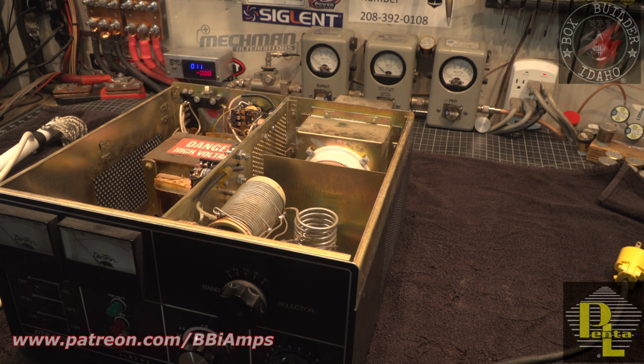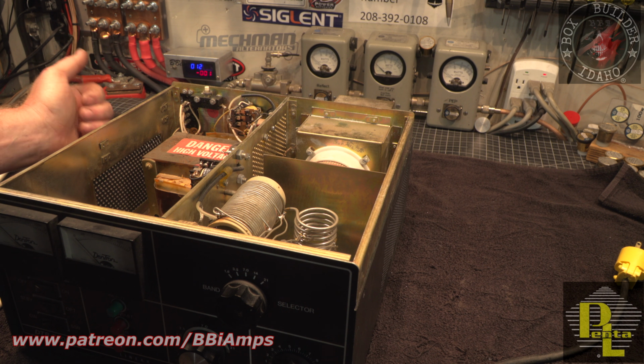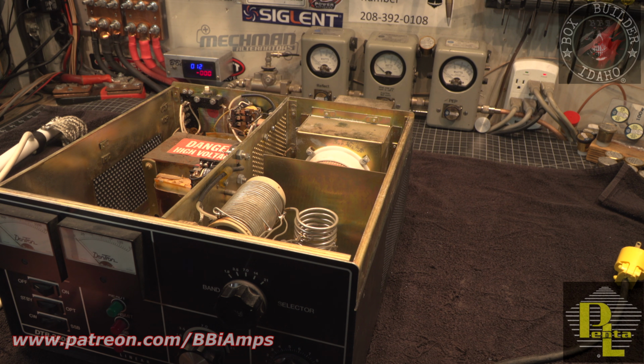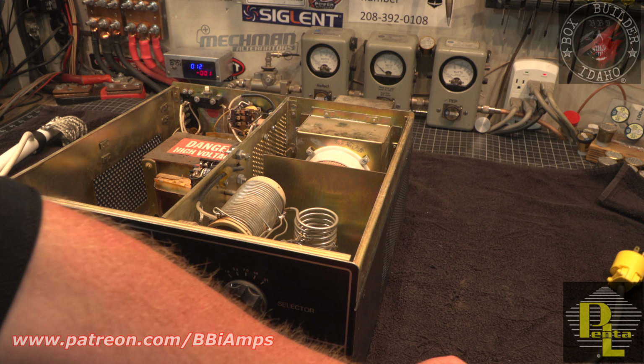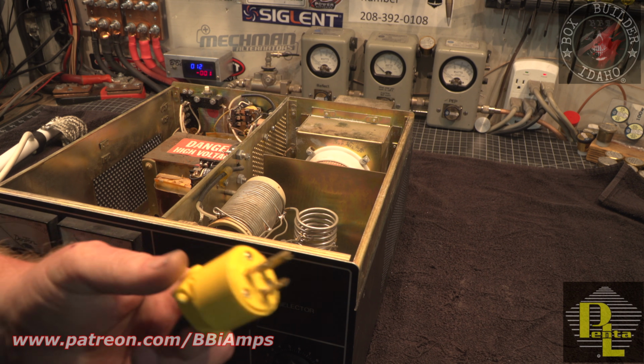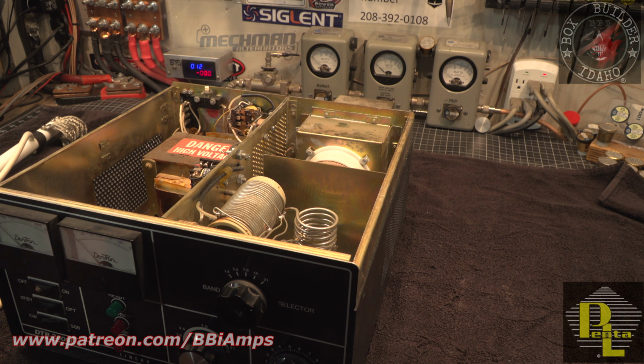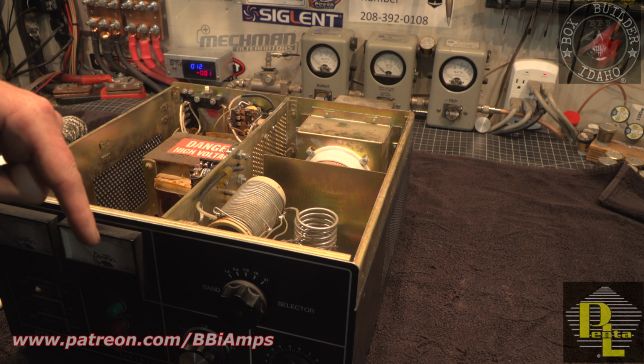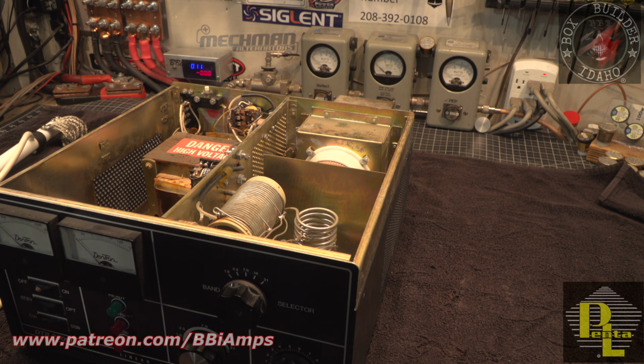They'll have a shorting bar in the high voltage to where if you lift the lid, the armature will fall down and short against the high voltage. And on top of that, when you lift the lid off, it also will activate, usually on this side of the cabinet, a little micro switch, and it'll make sure nothing can go to the power supply. Those two things are there to help try and keep you alive. A little micro switch on the back corner is to make sure that this is disconnected. The little shorting bar that's on the inside guarantees that the high voltage has gone to the case. We have the same thing in the SB220, the Drake, the Henrys, the Collinses, all of those things. They are there to try and keep you alive. Because once you take that shield off, and if this thing is still plugged in, you're very close to getting to meet God and it hurting the entire time while you die.